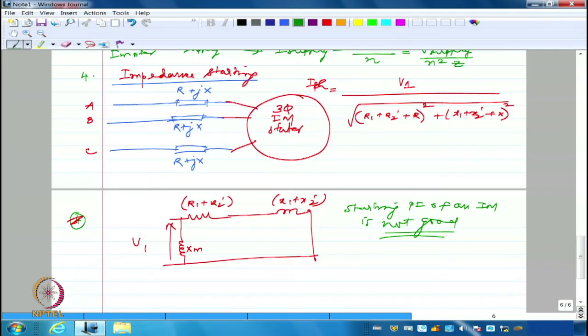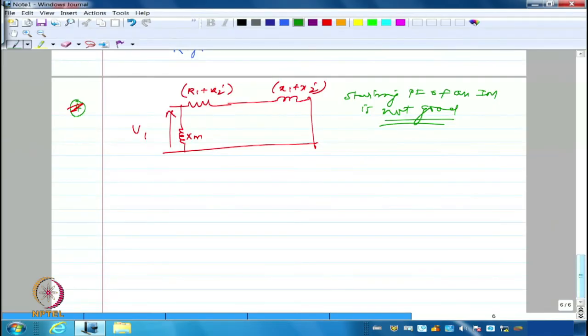If I have a good cooling arrangement but want to take care of the power factor much better, I might include a larger resistance and smaller reactance. But nevertheless, this is a lossy method. It's not going to give you good starting torque performance, as the starting torque is still limited. That's one of the problems with this method of starting. So impedance starting can include large R and less X, less R and large X, or all of them almost equal, depending on the requirement.